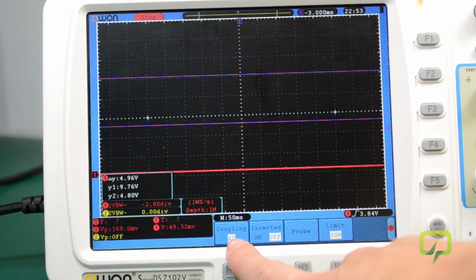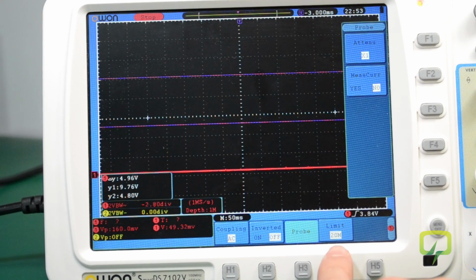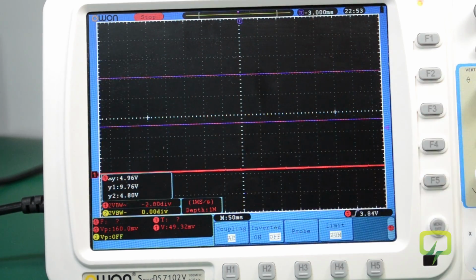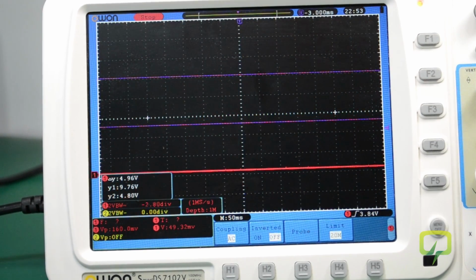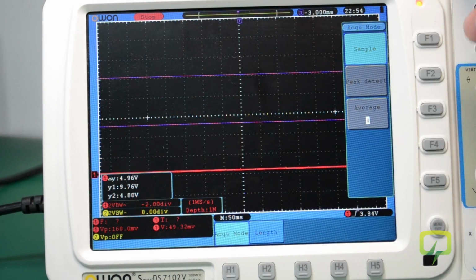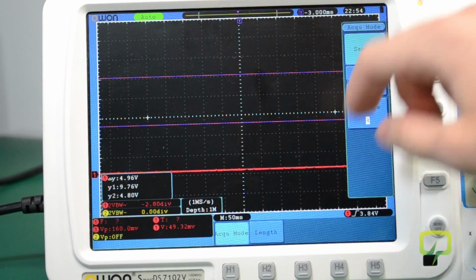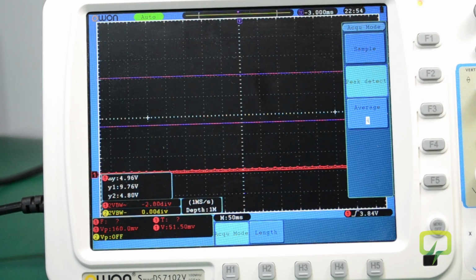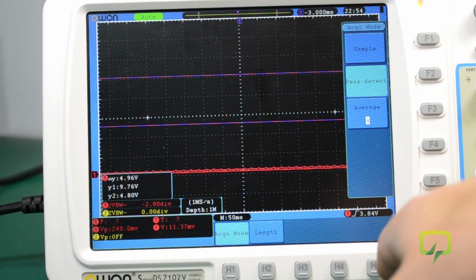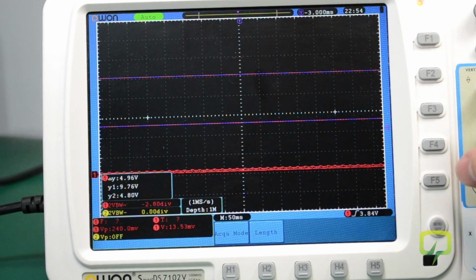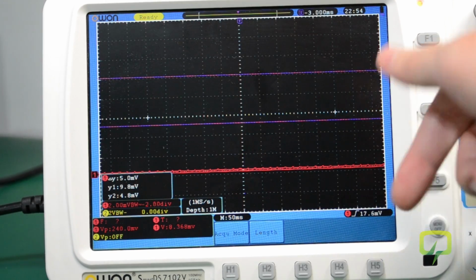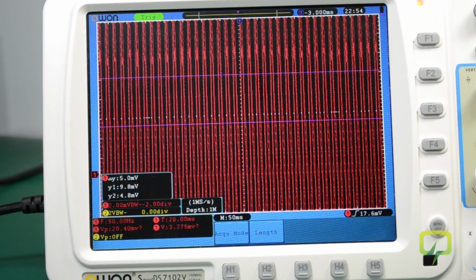You want to use AC coupling, ×1 probe and bandwidth limit on, because these noise figures are usually given for bandwidth limited measurements. As for acquiring the signal, you generally want to be in peak detect mode, because we want to measure all the noise peaks. So peak detect is the best mode for measuring the output noise of a power supply, and you should go to the lowest vertical range of your scope, which is in my case 2 millivolts.